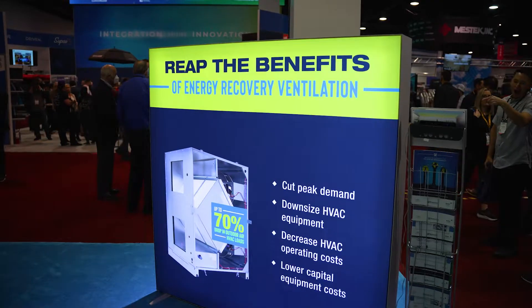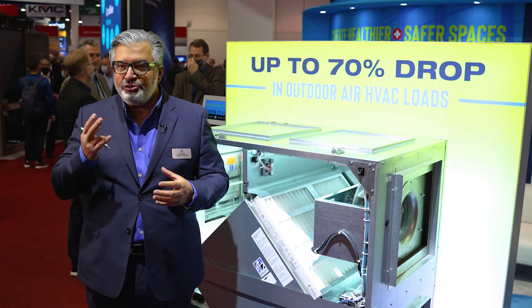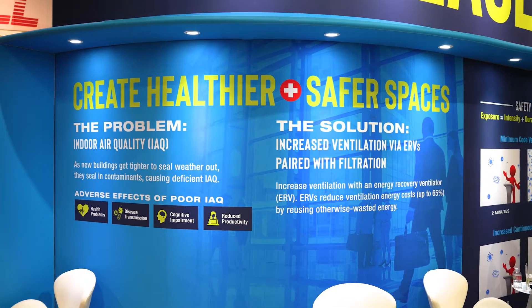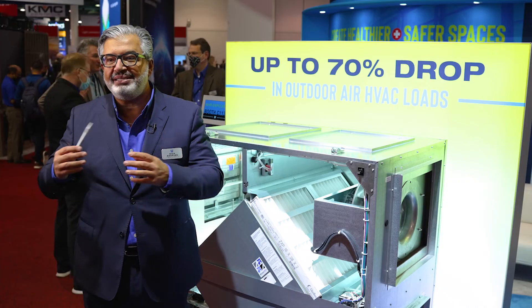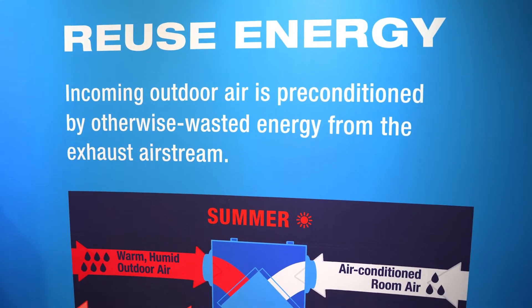RenewAire ERVs are a technology that uses a polymeric core which transfers two types of energy. Number one is sensible energy, which is a technology readily available by many other corporations. But with RenewAire technology we also transfer latent energy, so we call our systems a total energy device rather than an HRV, which is a sensible energy device. This allows you to capitalize on both sensible energy and humidity in both summertime and wintertime conditions.